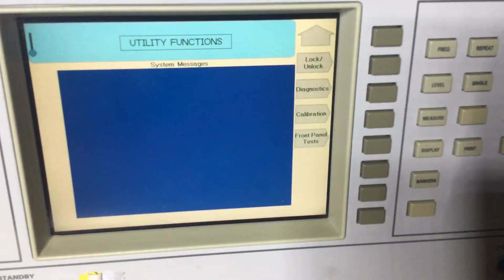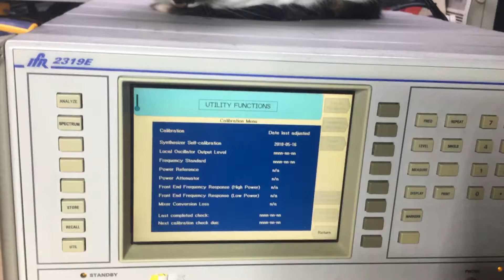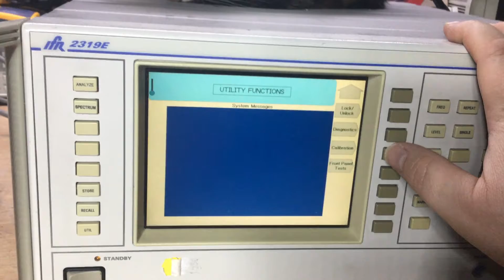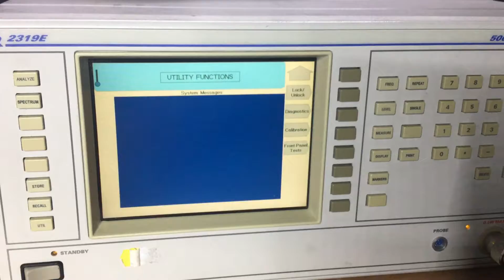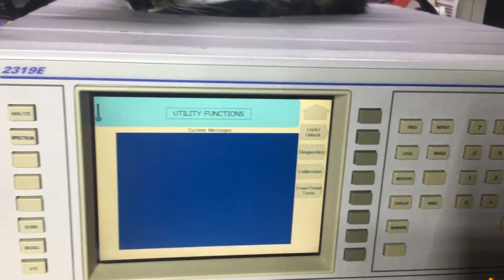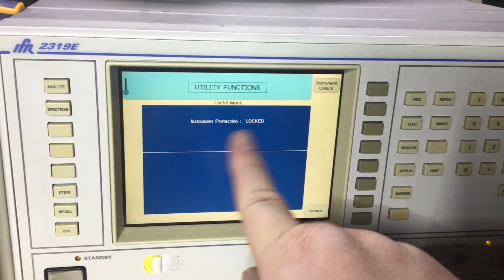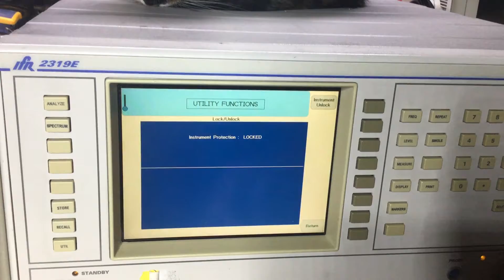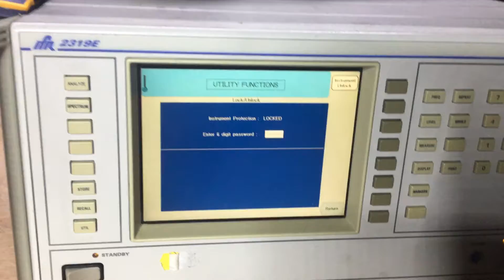So when you go into calibration, for example, it goes into this menu, and basically you can go into different things now. I've done it so it's on like a timed thing. So utility, I think you can select a calibration, but it's unlock, that's it. It's this button here where you lock and unlock the menu there, in order to get into the calibration features, because otherwise, you see, they're all greyed out. When you go into calibration, all these are all greyed out, so you can't do anything. So you have to lock, unlock, and then you have to put a code in. So then you have to do instrument unlock, because it's locked. So you press instrument to that.